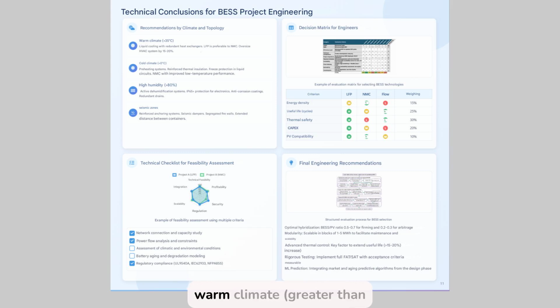BESS. For a warm climate, greater than 35 degrees, use liquid cooling with redundant heat exchangers. LFP chemistry is preferable, with better thermal performance. Oversize the HVAC by plus 15-20%. For a cold climate, below 0 degrees, an active preheating system is required, with thermal insulation of ducts, cables, and cells. NMC is not recommended: high capacity loss at low temperatures.